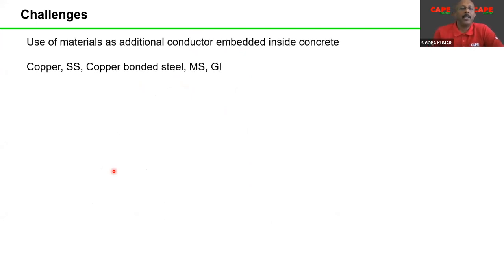Now, when it comes to embedding or using natural components, we face a lot of challenges. The first one: if you read the standard, it allows materials such as copper, stainless steel, copper bonded steel, MS, meaning a bare steel conductor, and galvanized steel. All these materials are allowed. But for the usage of each of these materials, some specific recommendations are also made in the standard.